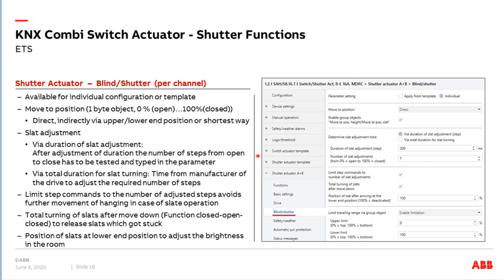On the blind/shutter parameter page, you can run the drive to any position via a one-byte group object — 0% is open, 100% is closed. You can go directly from 50% to 80% or 30% with no problem. You can also choose to go via the upper or lower end position first, or via the shortest way, before going to the next position. This can improve positioning accuracy and is fully adjustable here.